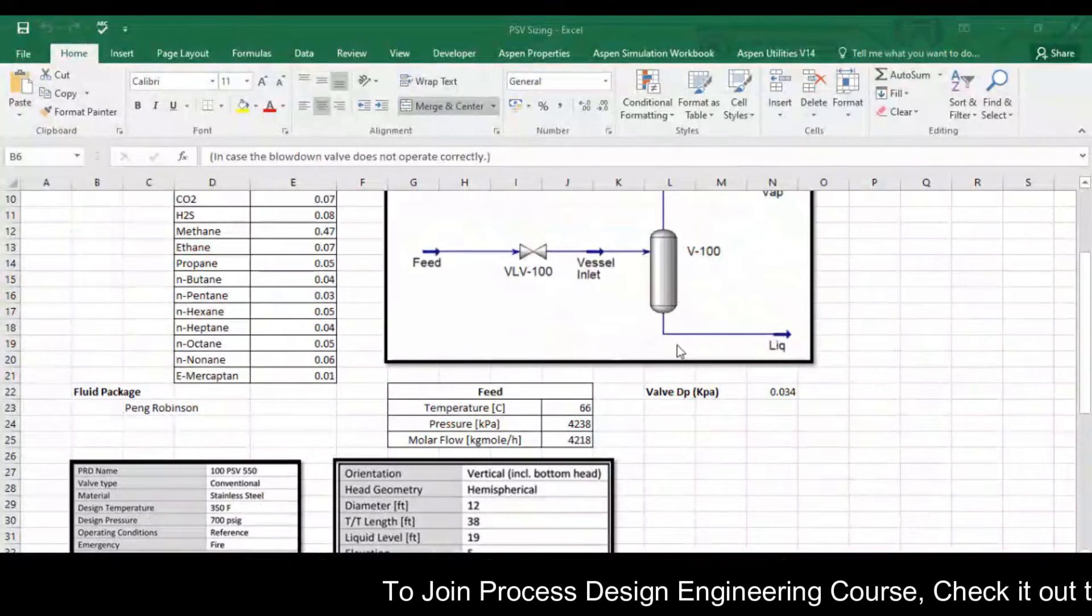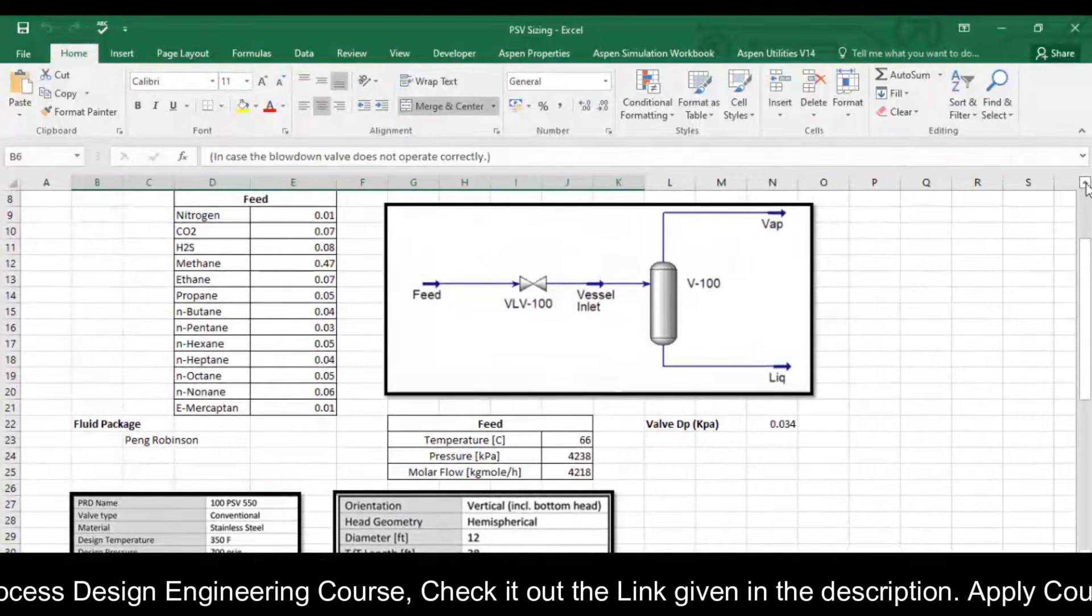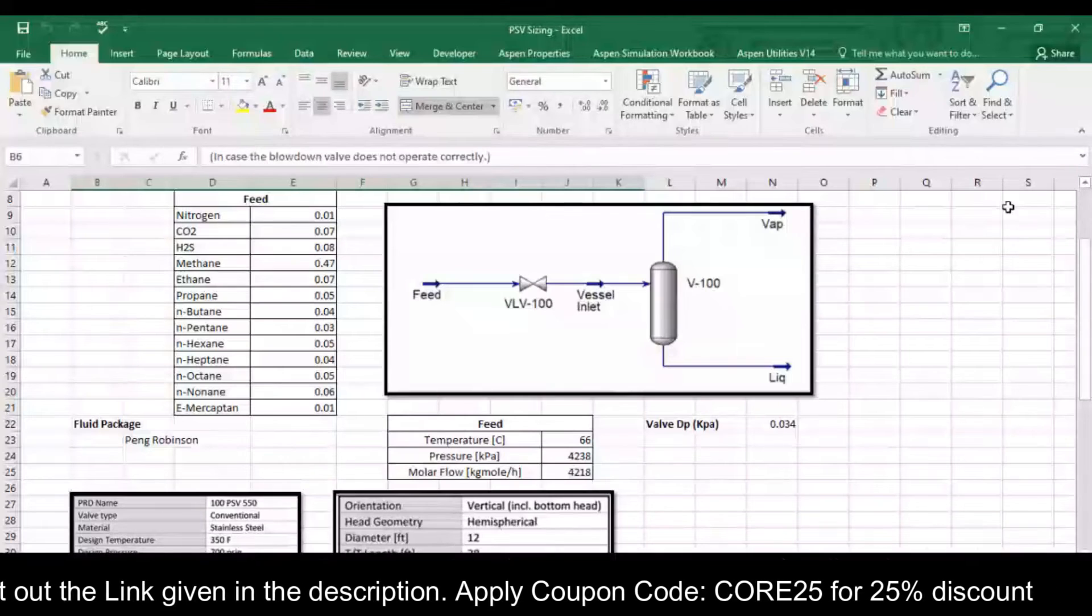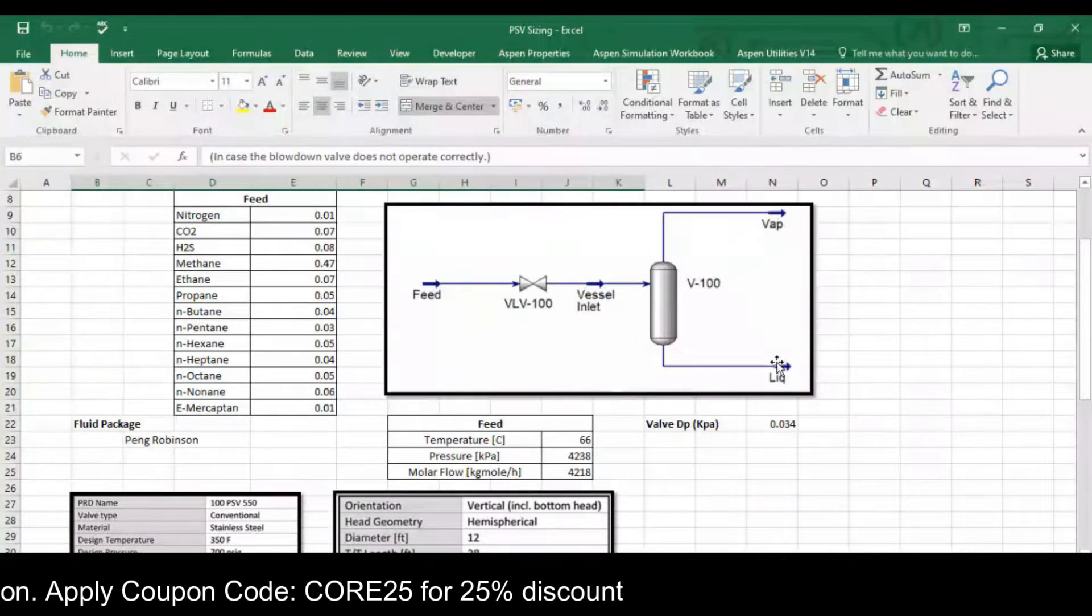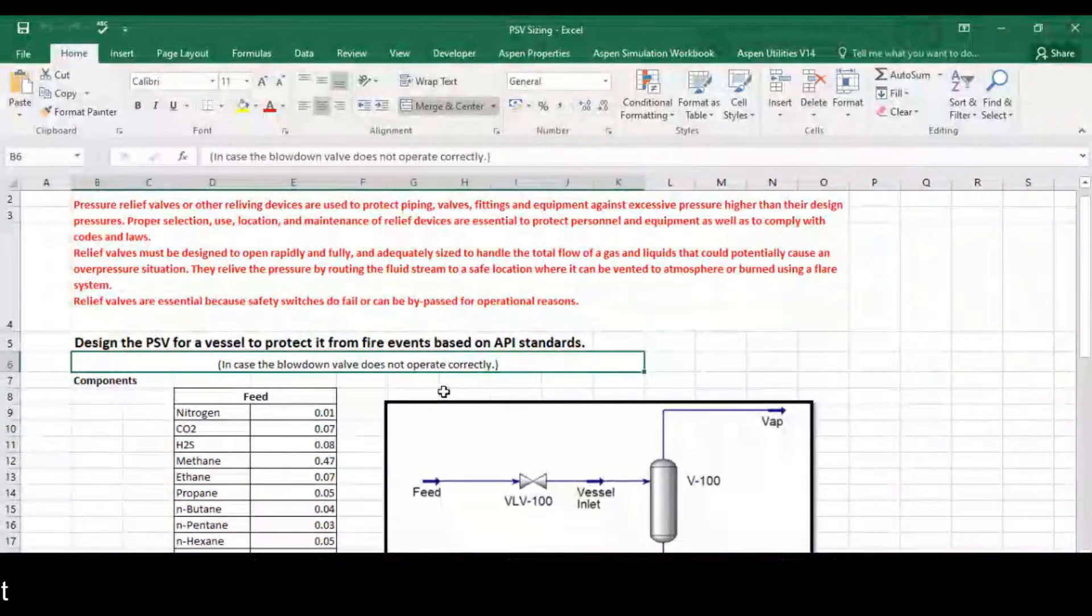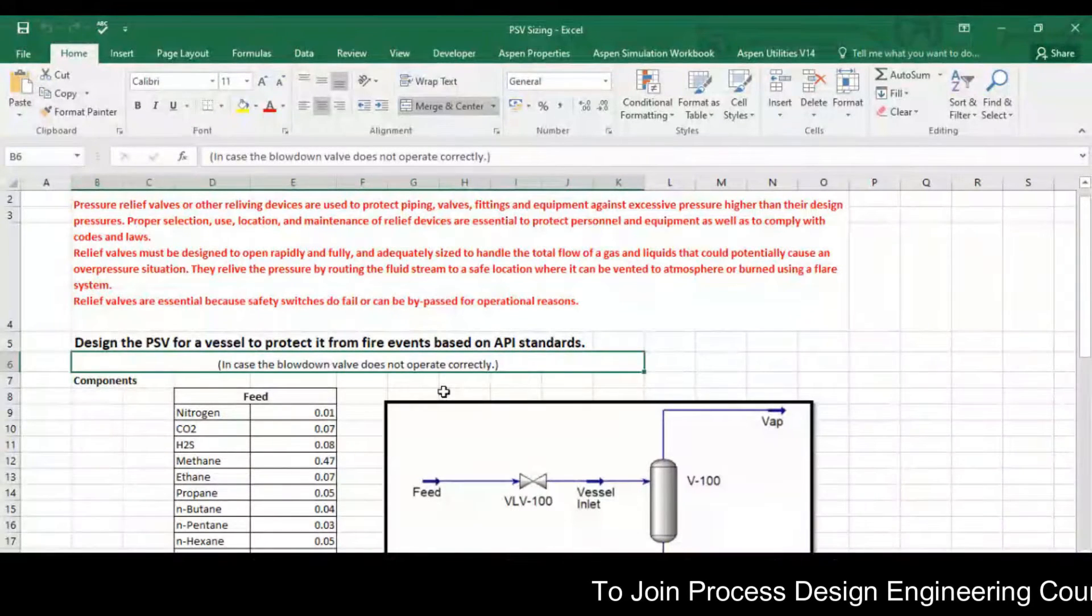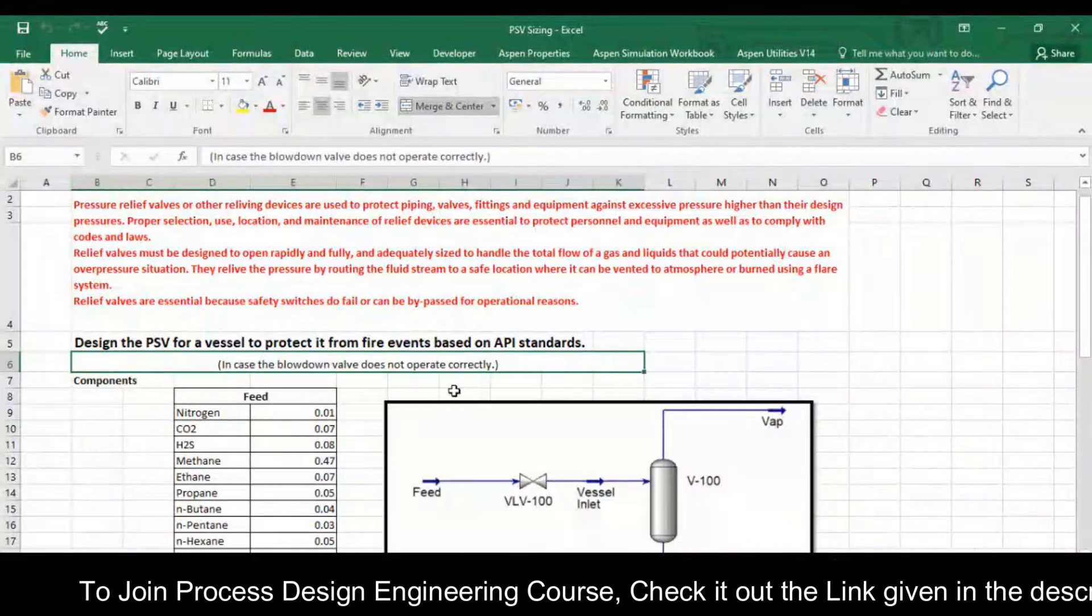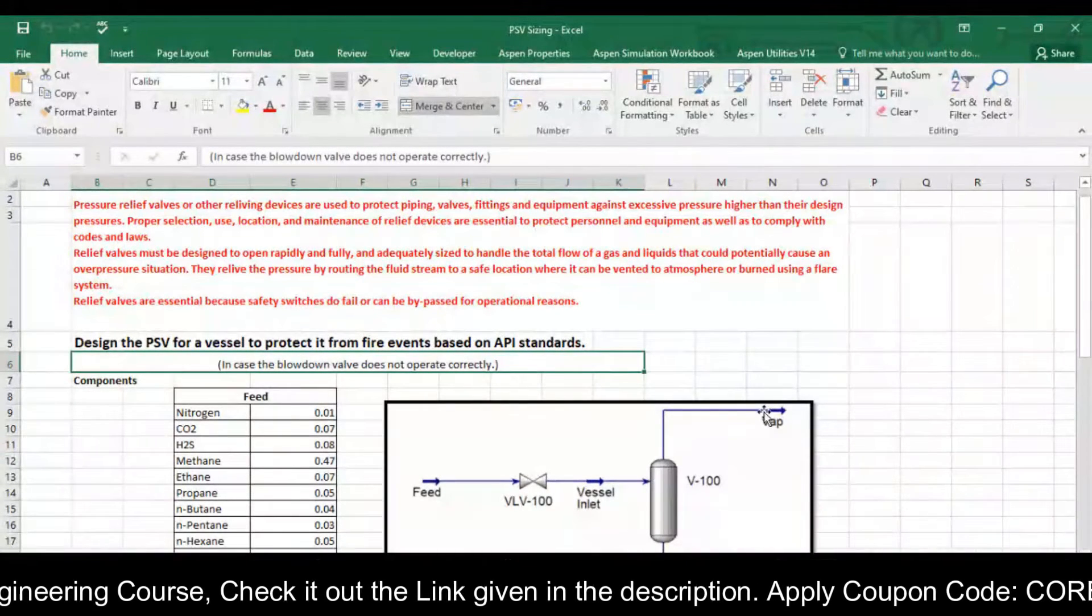So this is our flow sheet. We have the feed stream which is connected with the vessel and we are getting vapor from the top and liquid from the bottom. We will try to design a PSV for a vessel to protect it from a fire event based on API standards. In this particular case blowdown valve does not operate correctly, it means the total flow will pass through the pressure relief valve.